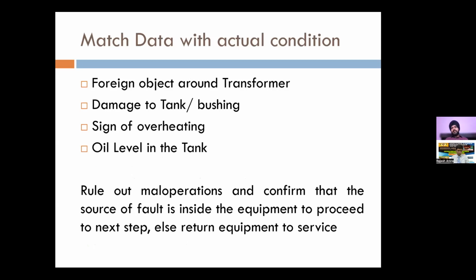Now, once this tripping has happened and you have done some initial investigation within your control room or at your remote operations station, then you need to correlate these factors with the actual condition at site. Somebody needs to go out and check if there is any foreign object around the transformer. There have been incidences where monkeys, peacocks, birds, or some object have come flying from outside the station due to systemic conditions, which have caused the tripping.